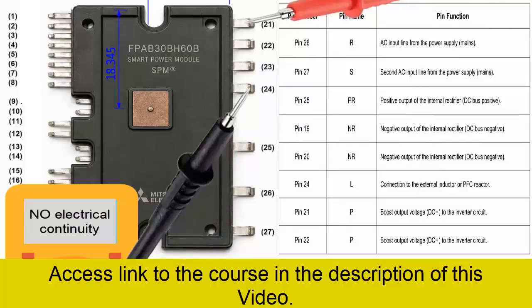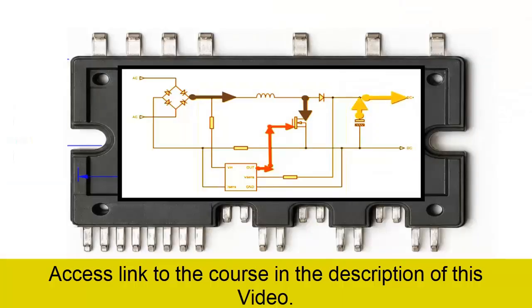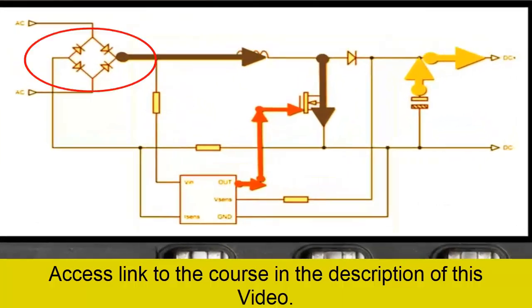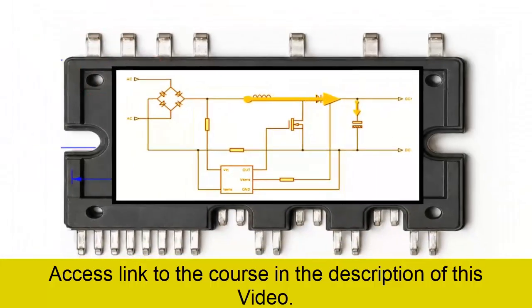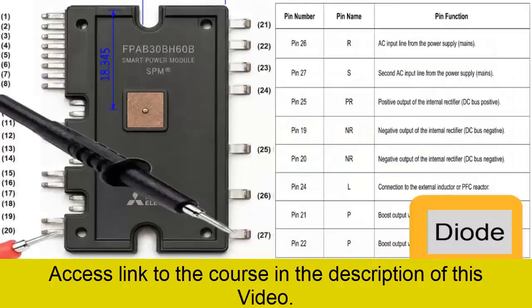Next, the input rectifier bridge test is performed. This test allows verification of the four internal junctions responsible for converting AC alternating current into DC direct current. Step A: place the red probe on pin NR, then touch pins R and S one by one with the black probe. Correct reading: the multimeter should indicate a diode drop voltage of approximately 0.4 to 0.6 volts.